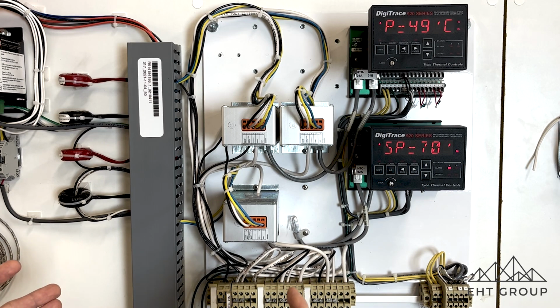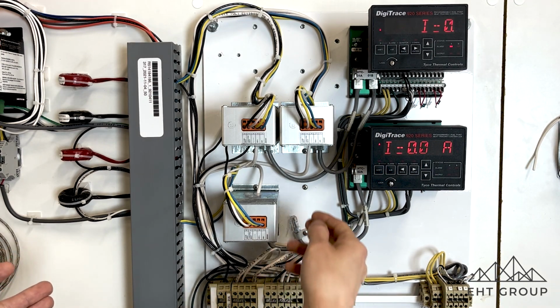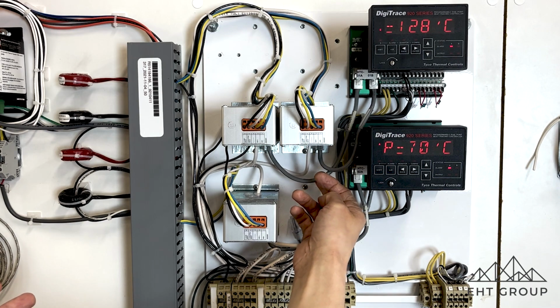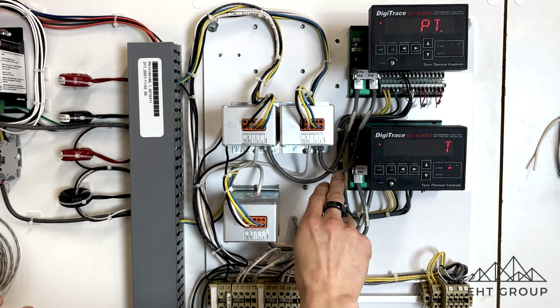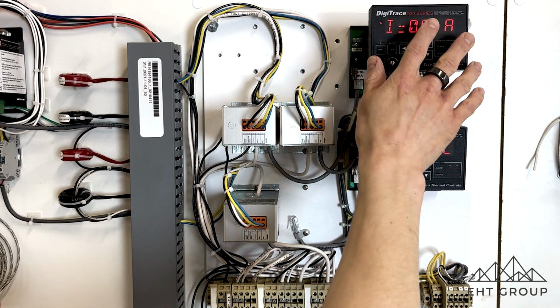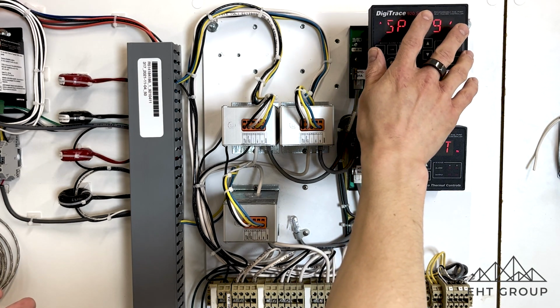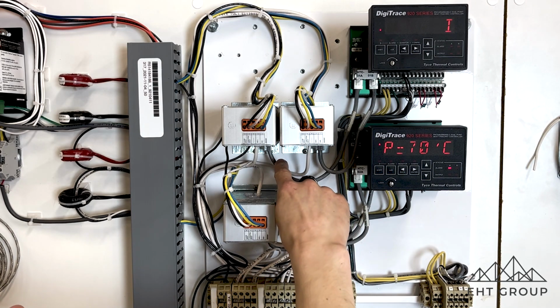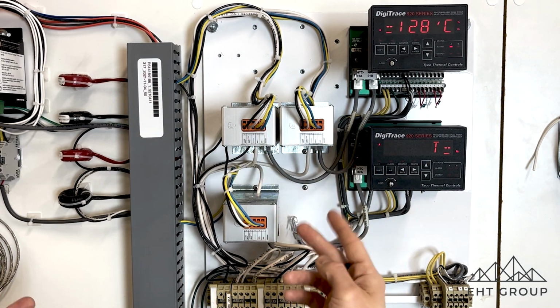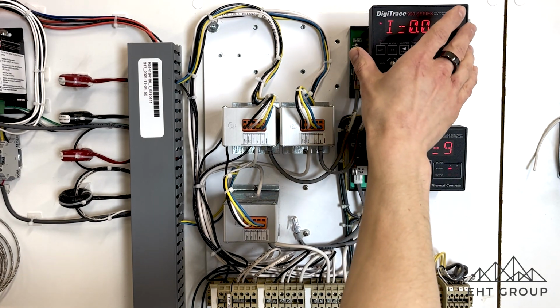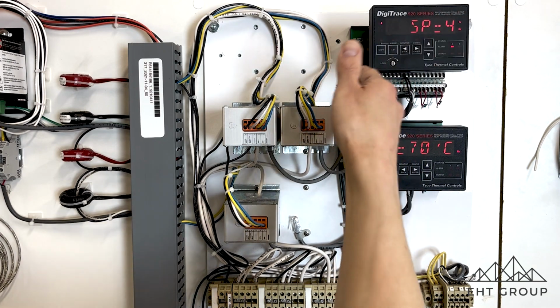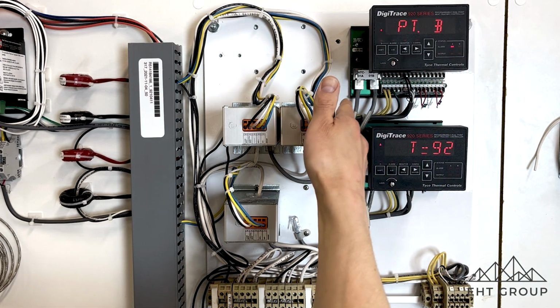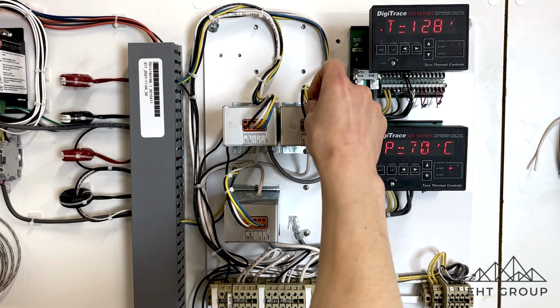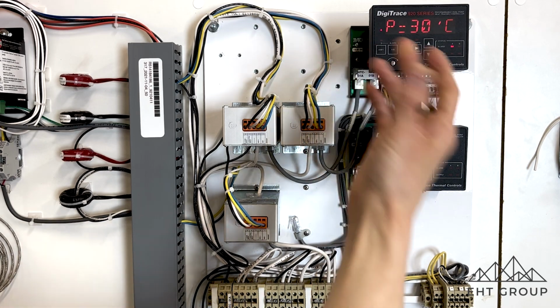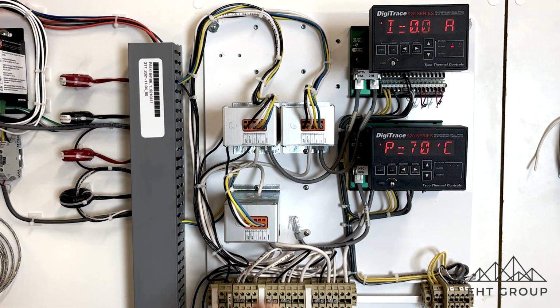So the next thing to chat about is that there is an RJ45, almost like a Cat5 cable, you'll see between the CT module and the 920 control board. This cable serves 2 purposes. Obviously, it's providing power to the 920 module, but the 920 is also reading current from the CT module, and it's also telling the CT module when to output onto the solid state relay, or when the solid state relay should be switching, or an EMR if it had an EMR module.